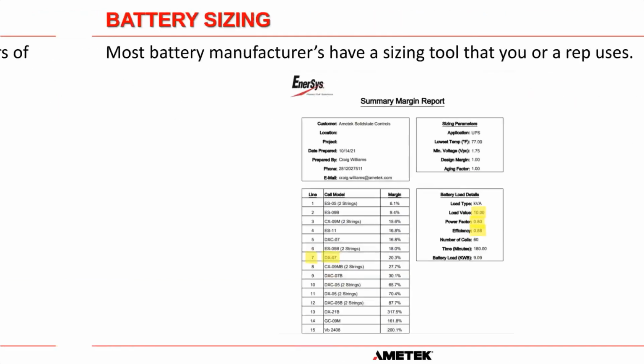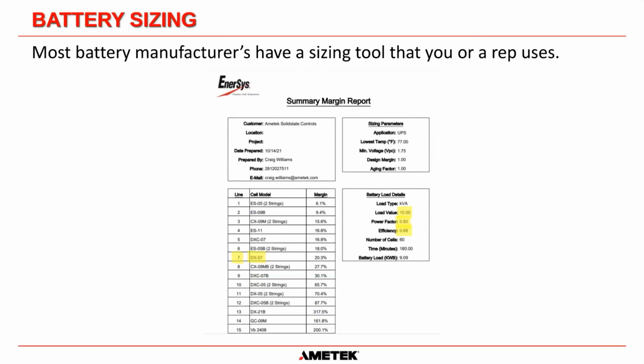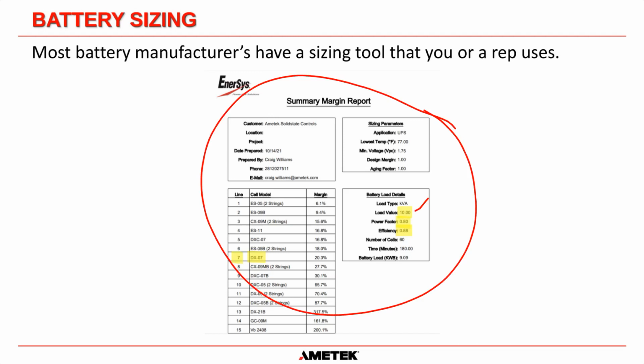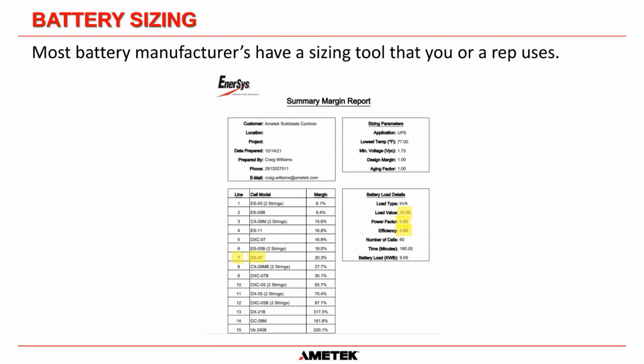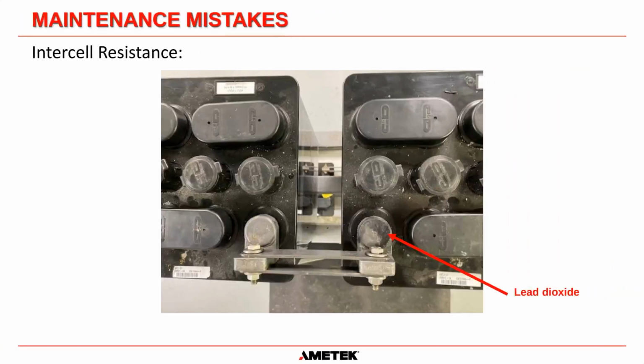So that's the hard way, should I say. The easy way is to get with EnerSys. They have a software package, and basically you can type in all of that data: a 10 kVA UPS, power factor of 0.8, inverter efficiency of 0.88, number of cells is 60, and it does all the calculations for you, and it lists all of these suggestions that you could do. You could do 2 strings of ES05, 2 strings of the CX09, but like I said, we had good experience with the DX, and the first DX that shows up is the DX07, which is the one that we chose, and there's actually a margin of 20.3 on there, so it is a little bit oversized. And then you can make a decision on which cell to use based on cost, if absolutely necessary as well. So that is how to size a battery.